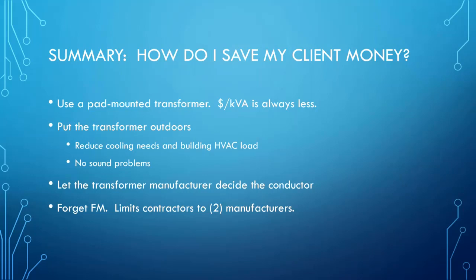I'm a fan of putting the transformer outside. This is one man's opinion, but if you're going to use a liquid filled transformer, put it outside, and I would use a pad mounted transformer. And here's why. No matter which manufacturer you choose, a unit substation transformer is going to be a custom engineered item. There are no catalog numbers for unit substation transformers. Every one of them is engineered to order.